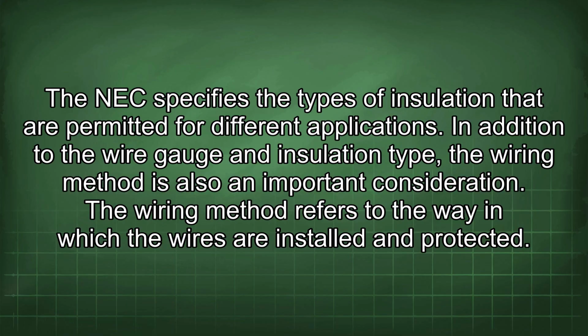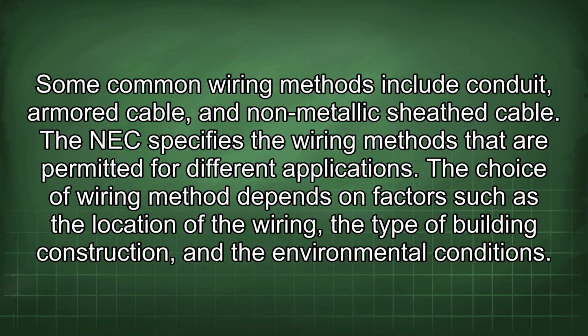In addition to the wire gauge and insulation type, the wiring method is also an important consideration. The wiring method refers to the way in which the wires are installed and protected. Some common wiring methods include conduit, armored cable, and non-metallic sheath cable. The NEC specifies the wiring methods that are permitted for different applications.